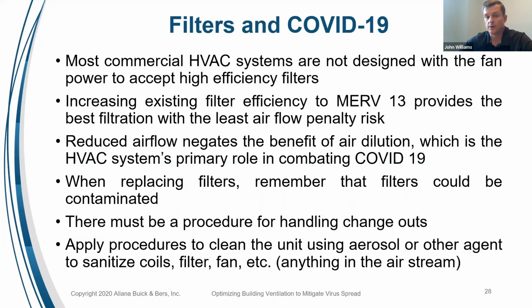As we go higher and higher in MERV ratings, the filter media becomes thicker and thicker, and it becomes harder and harder to move the air across it. Unless we have enough fan horsepower, we're going to end up decreasing our airflow, which negatively impacts our efforts to dilute the air and ventilate the building. Typically MERV 13 filters are going to be the best trade-off between filter efficiency and ventilation in our buildings. But when we go to change these filters, we have to remember a few things.